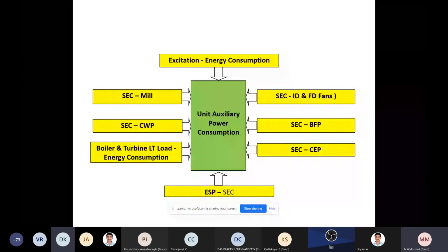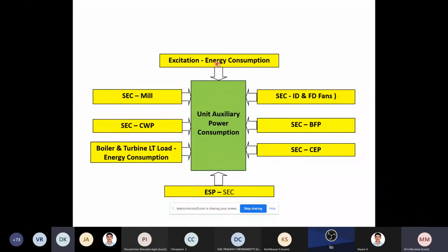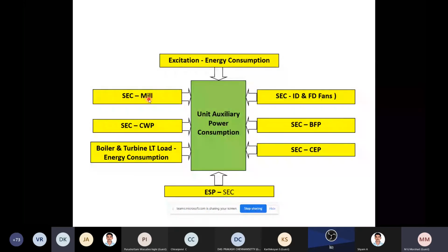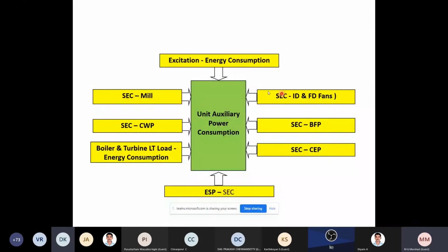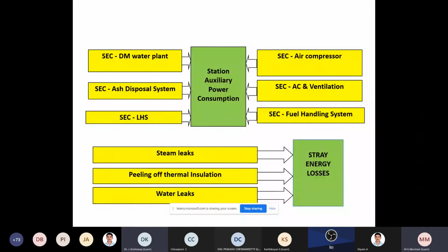Now, unit auxiliary power consumption is also very, very important. It has to be calculated accordingly. It will be influenced by the excitation energy consumption, specific energy consumption of the mill, ID and FD fans, boiler feed pump, CEP, boiler and turbine LT load, and ESP load. So these are all the electrical parameters which will influence the auxiliary power consumption. Then station auxiliary power consumption is also a part of the auxiliary power consumption. In such a case, specific energy consumption of the DM motor, air compressor, ash disposal system, AC ventilation, lignite and coal handling system, and fuel handling system. These are all the parameters to be given.